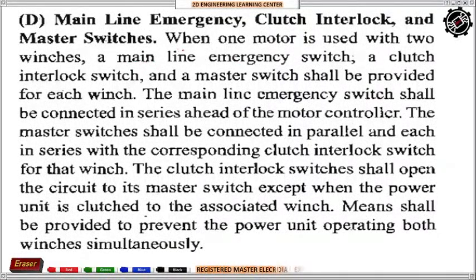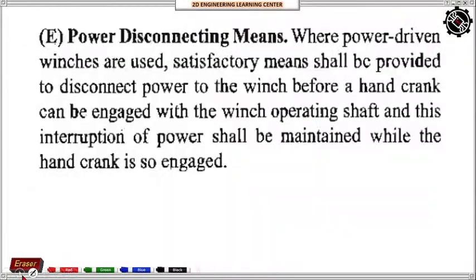When one motor is used with two winches, we should have a main line emergency switch, then the clutch interlock, then the master switch. Power disconnecting means: when power driven winches are used, satisfactory means shall be provided to disconnect the power. So we should have a main disconnect switch.